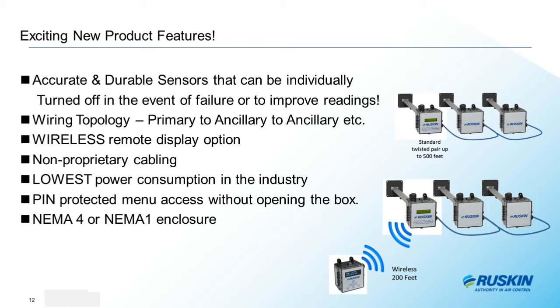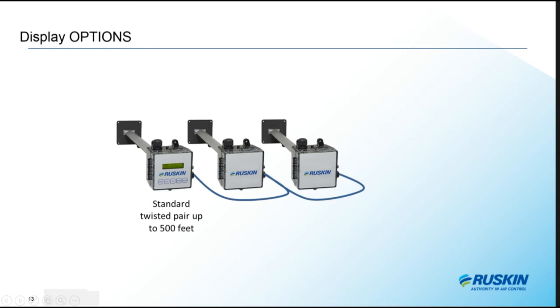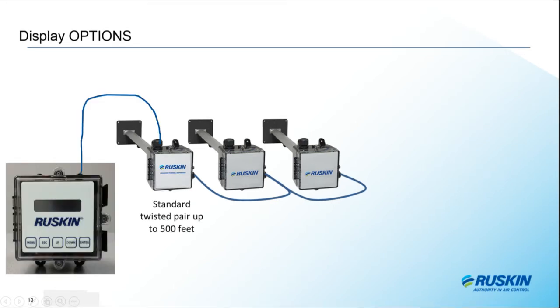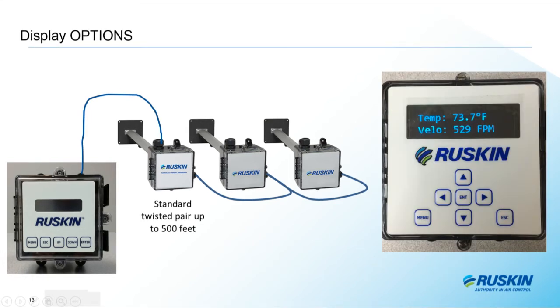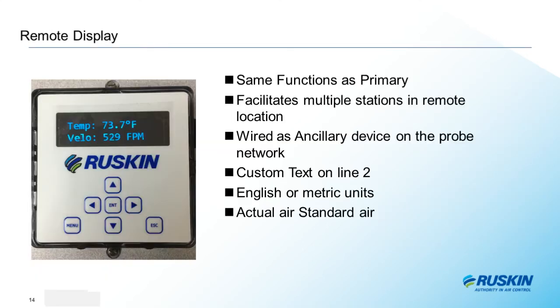Again, we have 4 display options. One is a primary probe with a display and any number of ancillary probes. This is the best choice when the installed location is easily accessible. We have a second option, and that is the wired remote primary controller and all ancillary probes. The primary is a separate box and is not part of the probe and can be wired up to 500 feet away. The third option is the addition of our wireless remote display, duplicating all the functions of the primary probe. This is also available as a wired remote display, so available as wired or wireless. The primary probe is available with or without a display. So we have lots of options here to fit your particular application and how it's going to be installed.